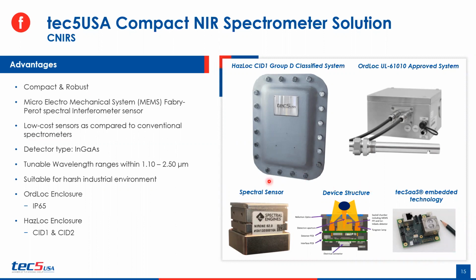So in addition to these components, these are equipped with MEMS or microelectromechanical system devices, and in this case here, a Fabry-Perot interferometer. So not only do these pieces of equipment allow for the compact size, but they also introduce a lower cost sensor as compared to conventional spectrometers. So this particular device utilizes the same InGaAs detector type, but a tunable wavelength range in the range of 1.1 micron to 2.5 micron. So that tunability allows you to tune in on the relevant wavelength region, which ultimately contributes to the lower cost. So you're focusing in on the relevant wavelength region instead of getting the full wavelength range for the measurement.